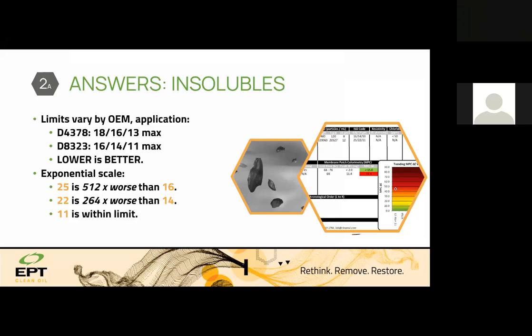One point on the ISO cleanliness code is that here, for example, we can do an analysis or diagnosis. You see 25, 22, and 11. So the number of particles above 4 micron and above 6 micron for this example is off spec, or out of the target.